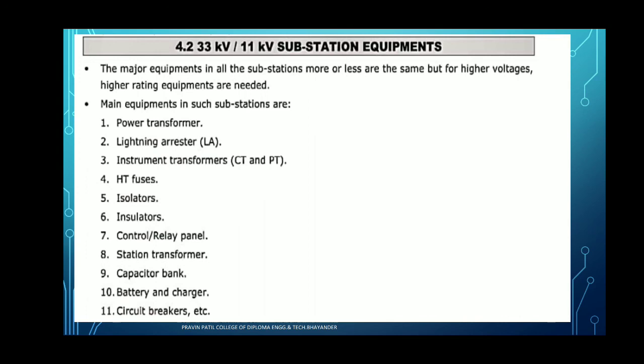Now we have to see the main components of the 33 by 11 kV substation: power transformer, lightning arrestor, instrument transformer, HT fuse, insulator, then control relay panel, then station transformer, capacitor bank, battery charger, and circuit breaker. These are the main components of the 33 by 11 kV substation. So these main components are installed in the substation for the continuity of supply as well as the protection of the equipment. Thank you, students.